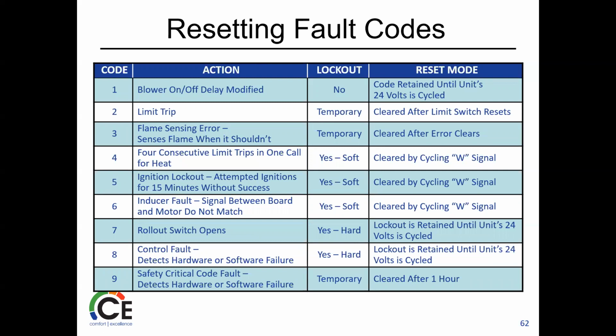Resetting the codes. If it's a soft code, we're really just talking about clearing the 24 volt call. So we're going to recycle 24 volts. You know, I just take the R off. It's up to you guys. You can do whichever one depending on what it is. But flame sensor error is temporary. It's going to keep trying until it gets to a soft lockout. If we get into a bunch of rollout switches, a hard lockout. So again, that's a 24 volt recycling.